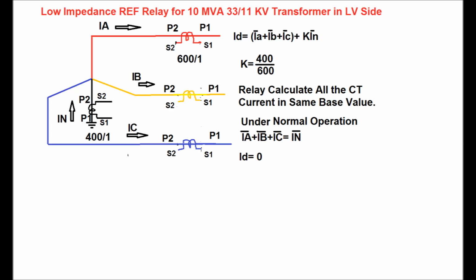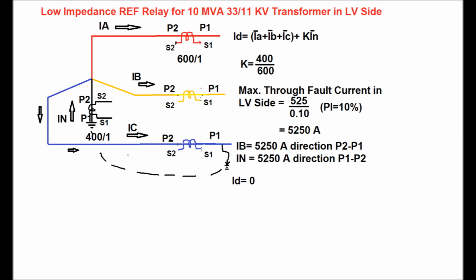Under normal condition, IA plus IB plus IC is equal to IN. So the ID, that is the differential current under normal condition, comes as 0, so it remains in a stable condition. Now consider a fault occurring in the blue phase under through fault condition. This fault current will flow towards the neutral point of the transformer. It enters the earth point, comes to the neutral point, and flows in the direction of the phase CT or bushing CT from P2 to P1 and towards the fault point, as shown in this diagram.